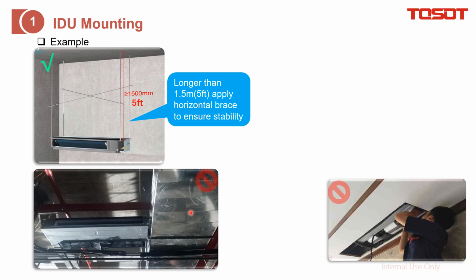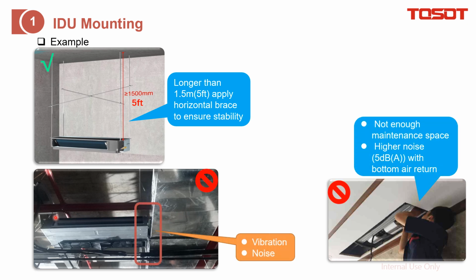The answer is no. For this one, you can find it. This is the ducted indoor unit. It already touched this air ductwork, which means during operation it will generate vibration and make noise. And for this case, you can also find that this is the indoor unit, and the service person will not have enough space to do the maintenance. Moreover, if this indoor unit just applies the bottom air return, the air volume should be fine, but the noise will increase by about 5 decibels A.